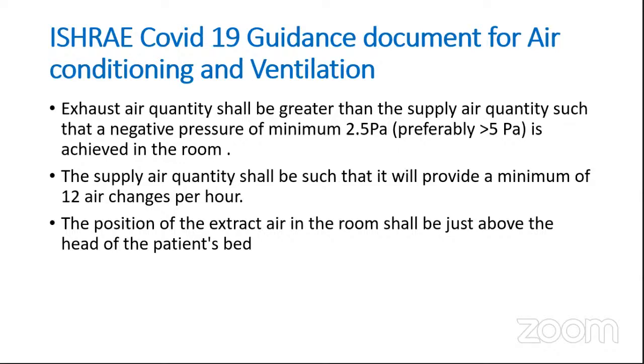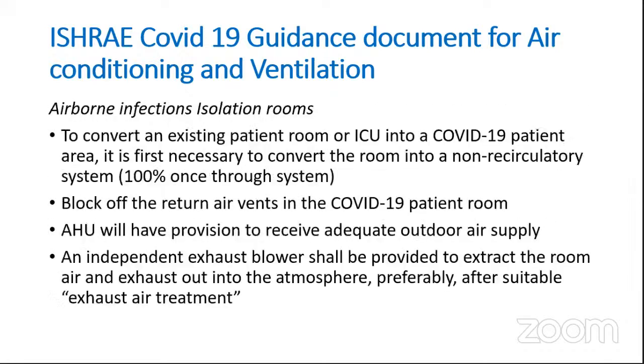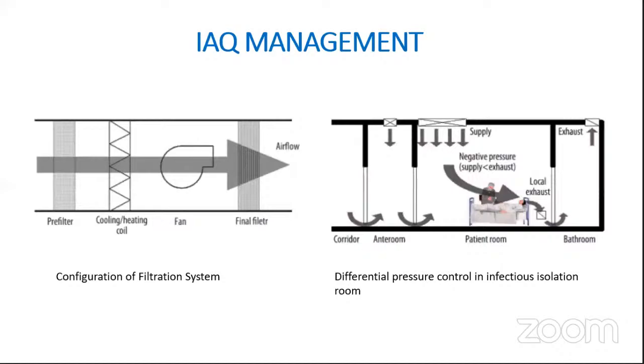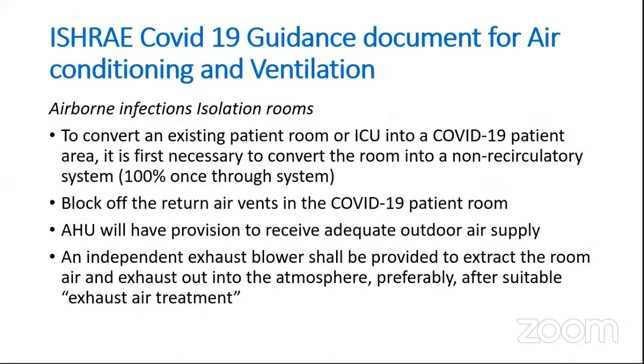The exhaust air quantity should be greater than the supply air quantity to have a negative pressure of at least 2.5 pascals. It should be around 5 or more than 5 pascals if we want it to be better. The supply air quantity should be minimum. If we are talking about a COVID hospital or room, it should have at least 12 air changes per hour. The position of the extract air, like you must have seen in the last pictures, should be above the patient's head.